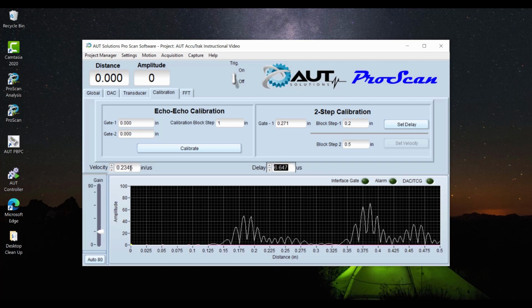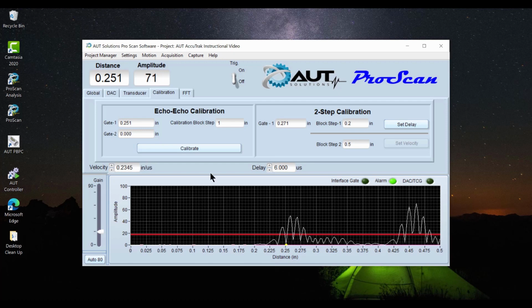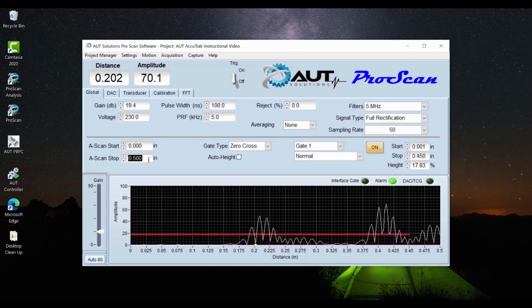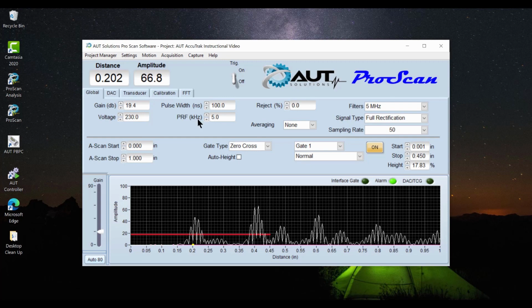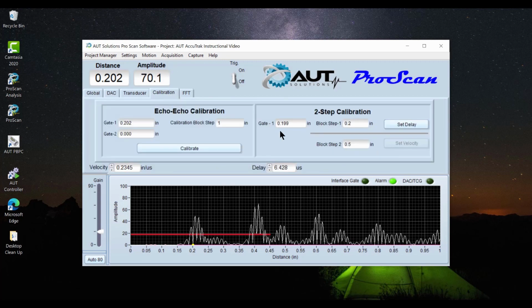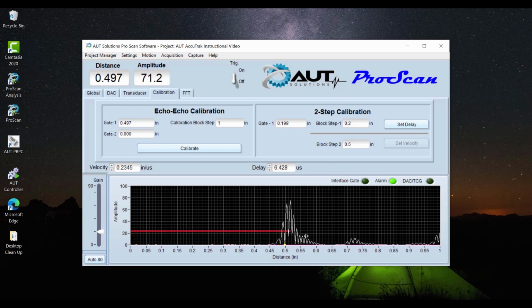We'll just punch in a value here, change our delay to 6, which is a good place to start. So he is going to move it back to the 0.2 of an inch spot, which we're at. So we will click set delay. One thing you'll notice, my screen range isn't long enough for this, so we're going to change that to 1 inch right there. Now he is going to move it over to the 1/2 inch step. Now one of the nice things with the newer software, you can drag this gate down if it's not long enough.